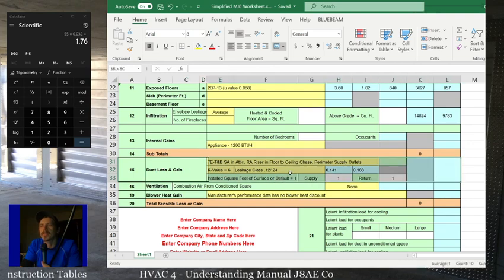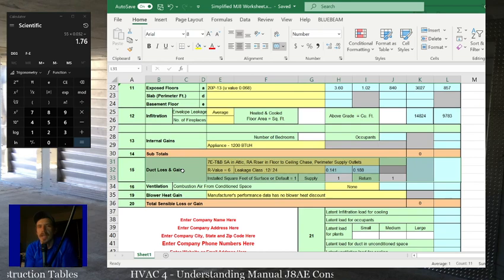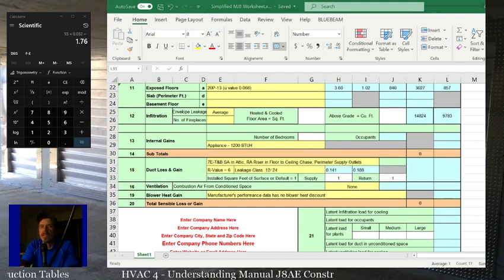One of your biggest factors, especially in ductwork that's in an attic, is you lose somewhere between 10 and 25% of your load into the attic, into the ducts. You just lose all kinds of the BTUs the system creates just in the ducts, which is what makes ductless mini splits so efficient, right? It's one of the reasons you see those 20, 25, 30 SEER numbers coming up with ductless units, because there's a lot of factors where they don't lose BTUs that you would lose otherwise with a ducted system. But anyway, that's where we're going to stop, okay?